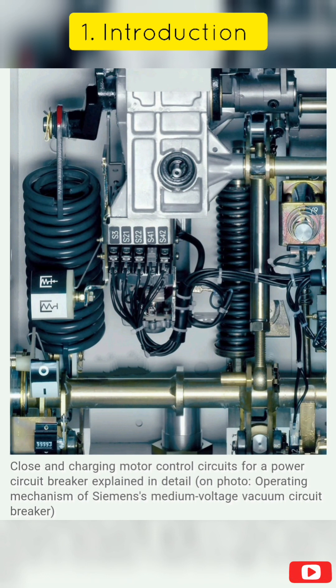Protection relays for medium voltage circuit breakers are not built within the circuit breaker like those for low voltage breakers, nor are they powered by the primary circuit's current. The safety relays are offered externally. Because of this, medium voltage circuit breakers rely on control power to precisely and consistently trip or open the breaker in the case of a malfunction. Since the availability of control power is critical to the protective function of a medium voltage circuit breaker, the control power source is extremely reliable.